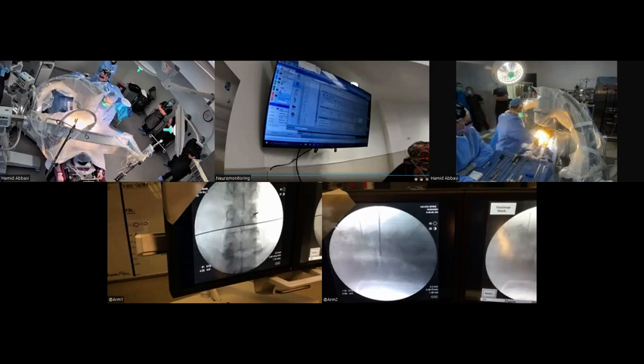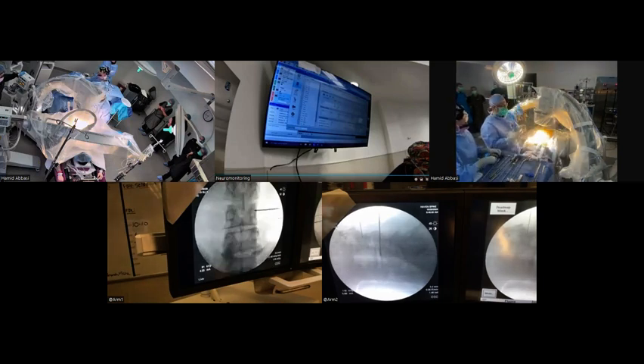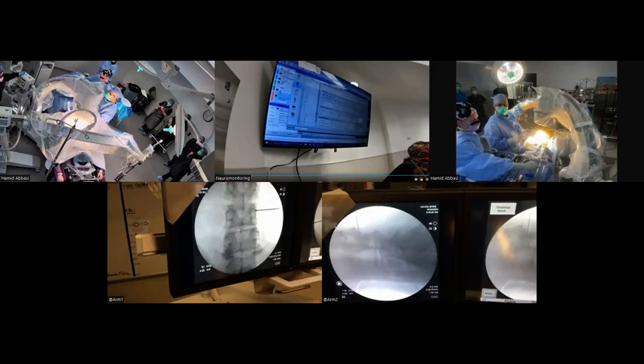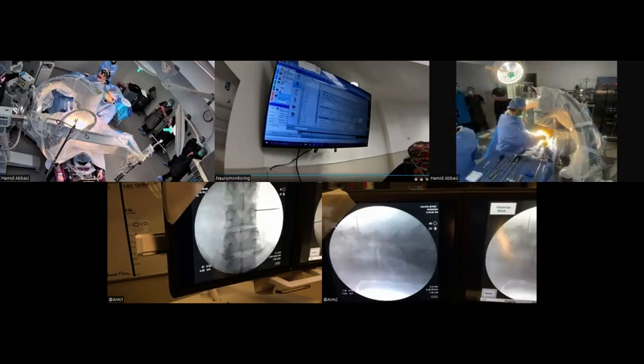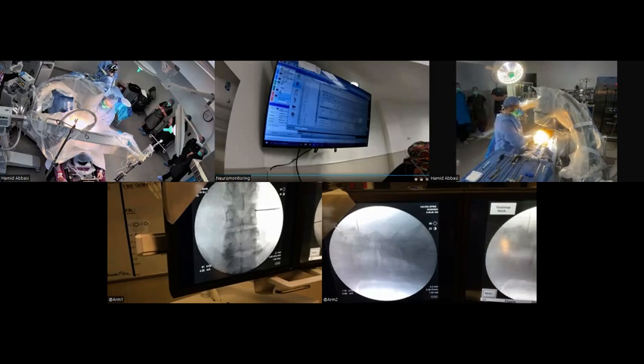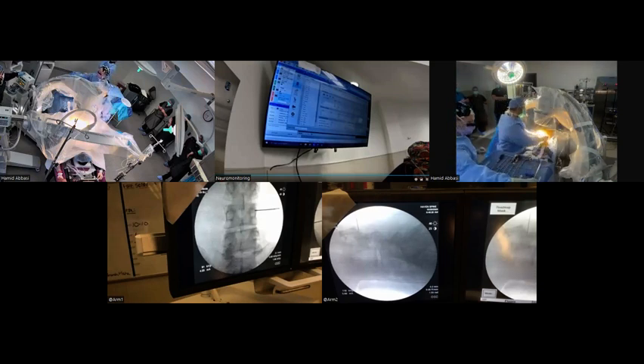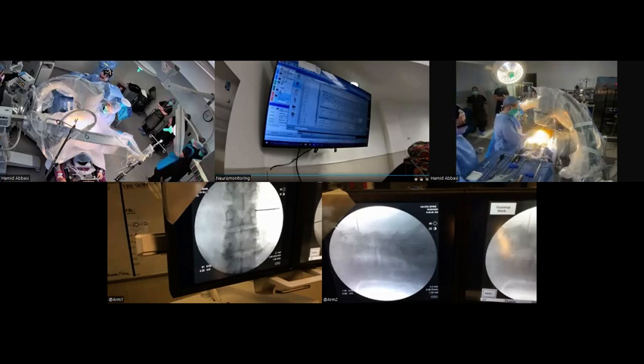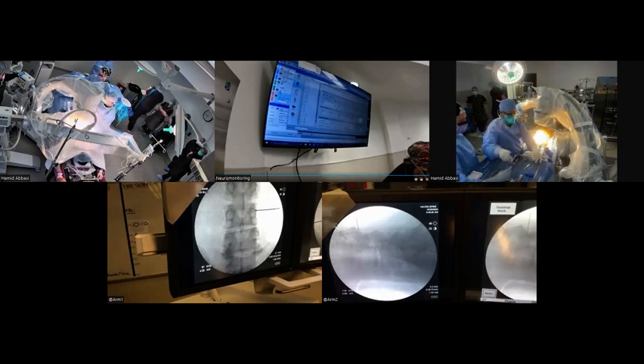We're going to mark that on the skin up and over the flank. And then we're going to take the wire, lay it across the patient's back, and figure out a rough estimate of the depth to the center of the disc. We're going to mark that from the center line out laterally. So that distance from the midline out laterally is going to tell us how far off midline to make the incision. The lordotic angle is going to show us a line on which to make the incision, and the intersection in the AP of those two lines is going to give us our target for the center of the disc.